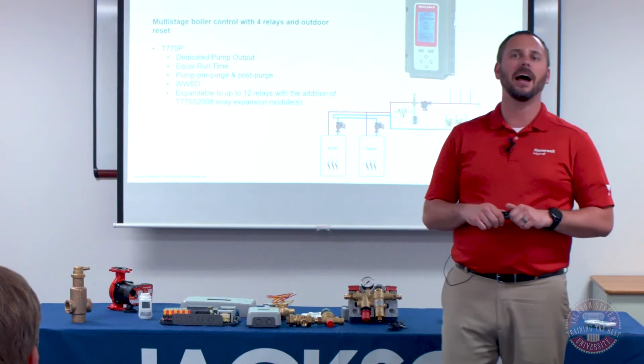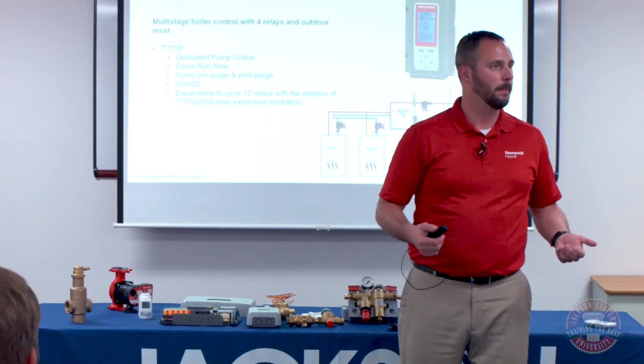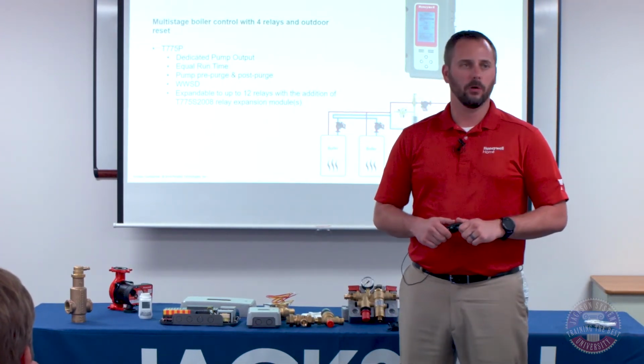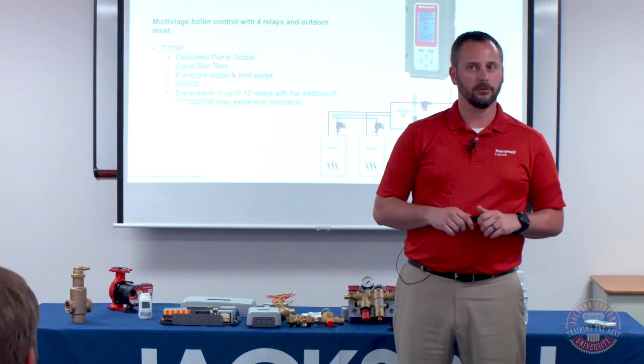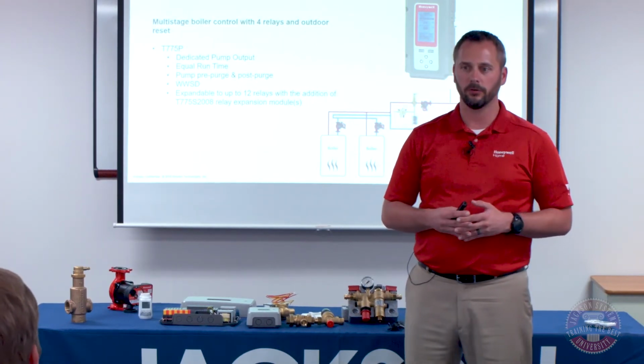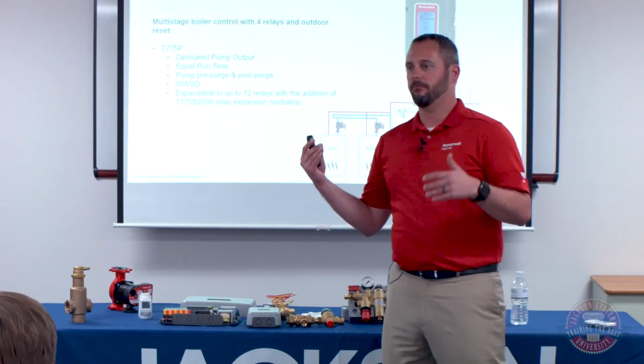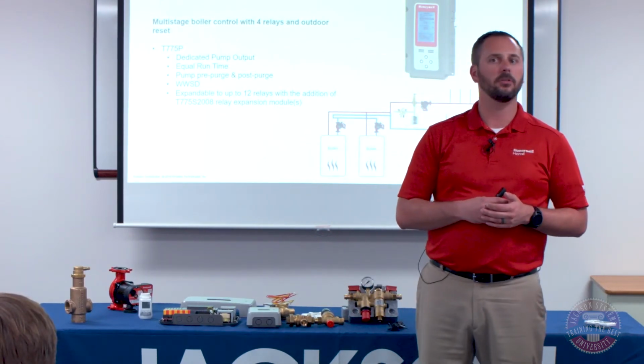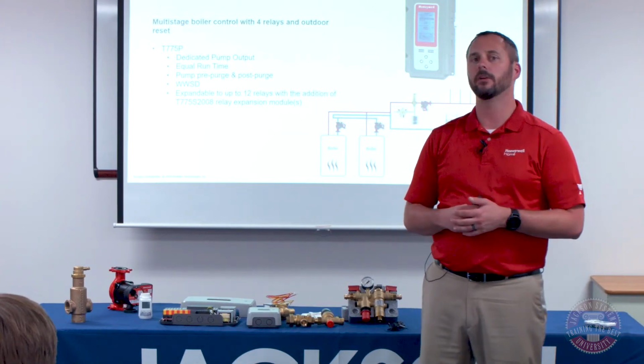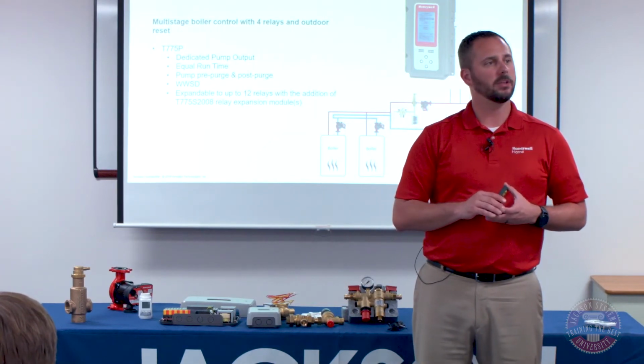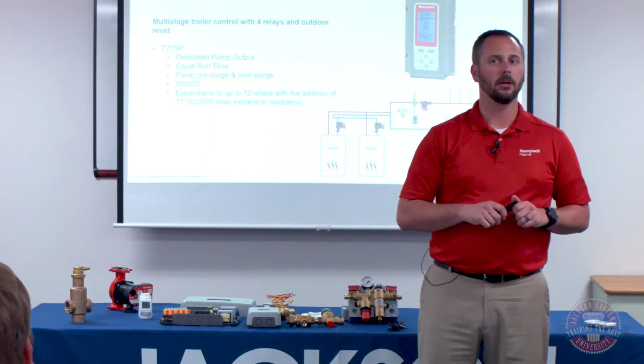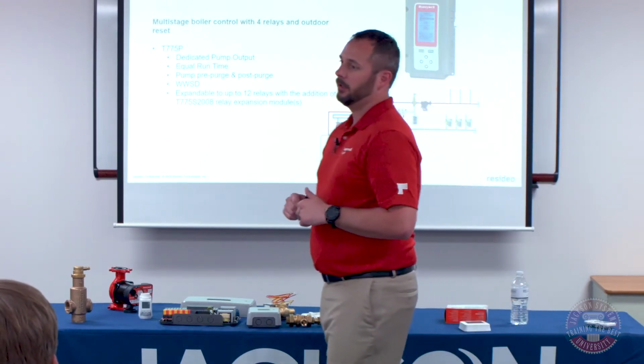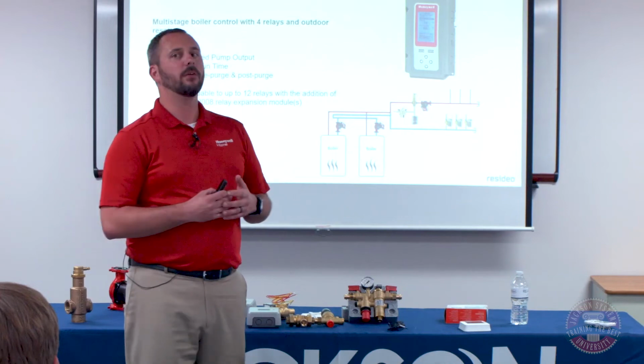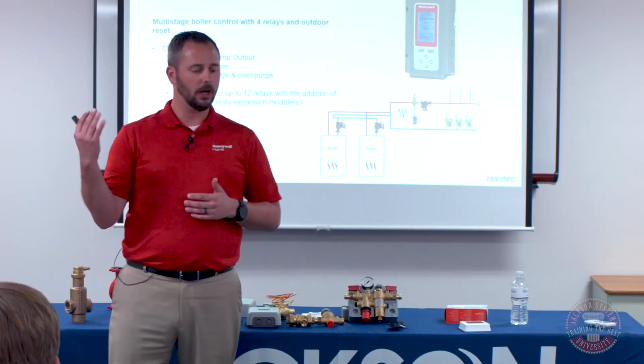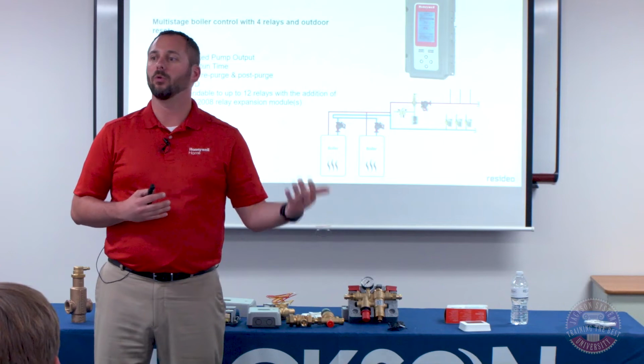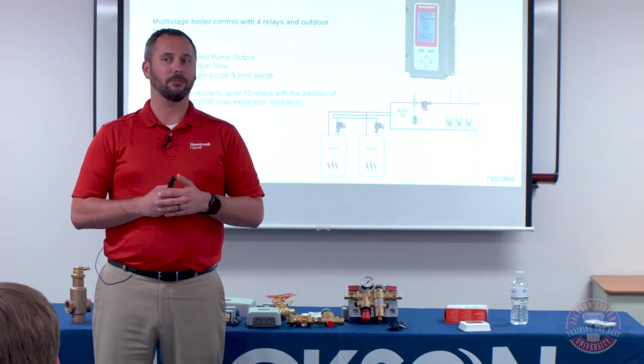So our T775, we make it in a bunch of different configurations. In the radiant world, we've got two of them that I see probably more than anything else. The first one is boiler staging controls. So whether it be a super high-end residential system that has two boilers, or light commercial, heavy commercial, whatever you're looking at, we have the ability with this control of handling boiler staging. With that, we can do lead lag, we can do equal runtime. There's different types of configurations. It's got warm weather shutdown, outdoor reset, and it's expandable.